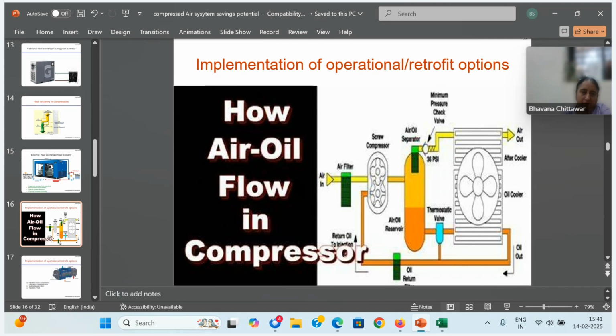Then please don't do it for a compressor under warranty, because suppliers, even though it is not their fault, will claim that you have retrofitted the compressor and spoiled it. So once the warranty is over, you can try, put a small restrictor. You start with 2% or 5%. Any proposal you do, do it small only. Don't jump to the highest thing. You restrict it, you record all the parameters: power, flow, pressure, load time, unload time, all the things you can. You can achieve 3 to 5% without any investment. All the investment is only on a washer, a Teflon washer or some stainless steel washer. So this is the thing.